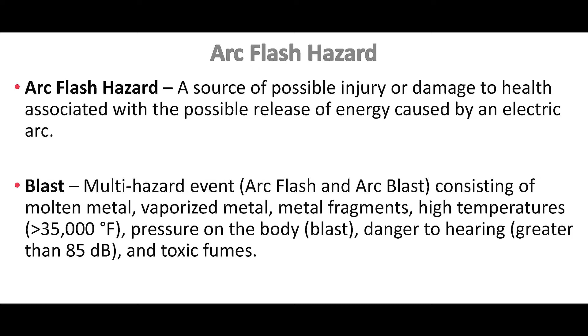Arc flash hazard is a source of possible injury or damage to health associated with possible release of energy caused by an electric arc. The intensity of it and how dangerous it is is based on the available energy or fault current, how long the arc lasts, and how far away from the arc you are. So the further you get away from the arc, the better. The shorter the duration of the arc, the better. And the less energy available, sometimes the better.